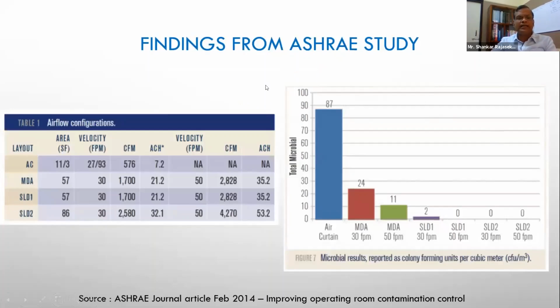If you look at the ASHRAE study, they talk about the single large diffuser and the medium multiple diffuser array. You can look at the area here, area in square feet. This is the area of the diffuser. As the diffuser size increases, the colony forming units, that is the microbial load on the operating table, keeps on reducing. At SLD1, which is 57 square feet in area, when operated at 50 feet per minute, it becomes 0. So we're talking about CFU per meter cube. And at 30 feet per minute, it's just got 2.